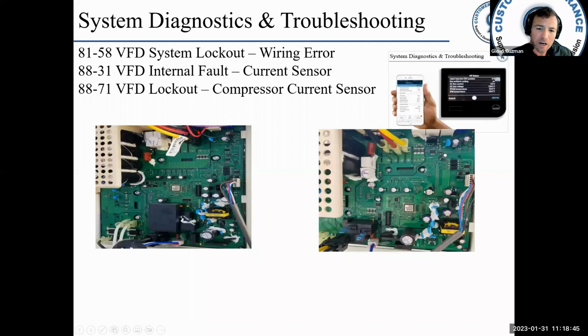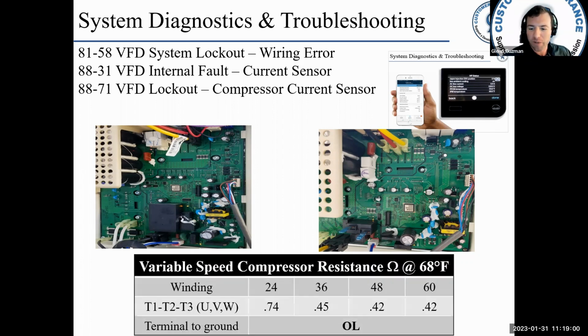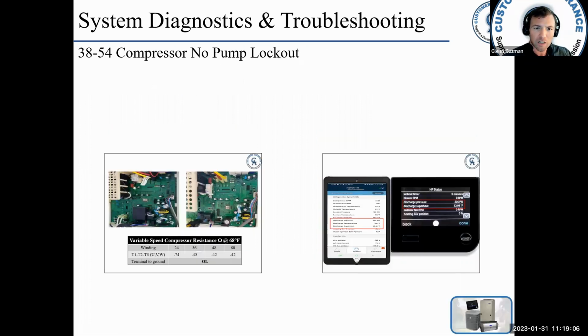You can see the picture on the left. You really cannot mess up that plug. It's polarized. The one on the right, yeah, you could inadvertently put one of the wires in the wrong spot, so that could happen. Could be an issue with the compressor itself. Check your winding resistance, ohm it to ground. Compressor no pump lockout.